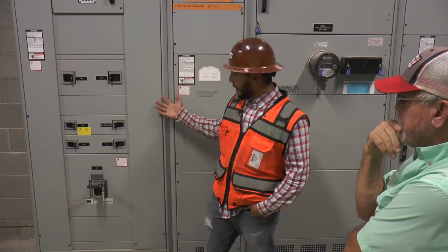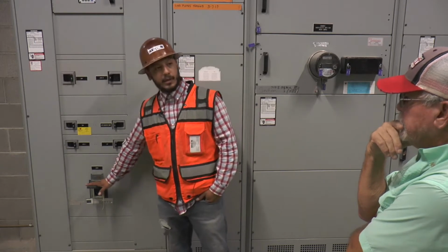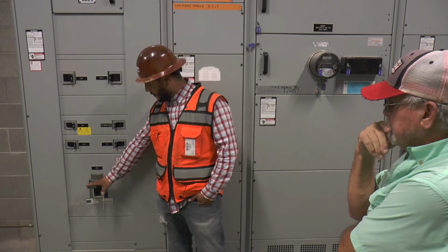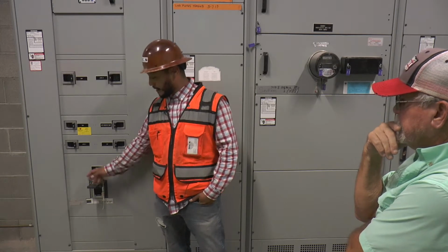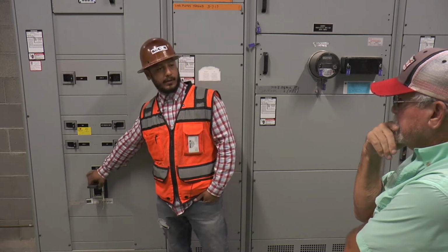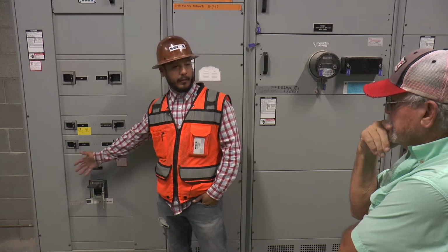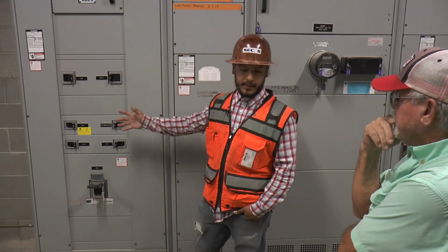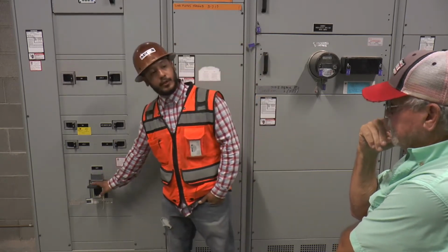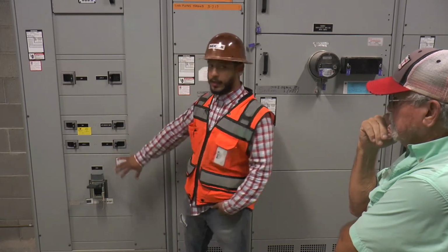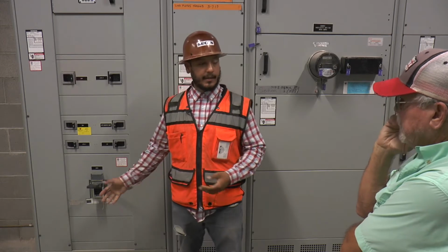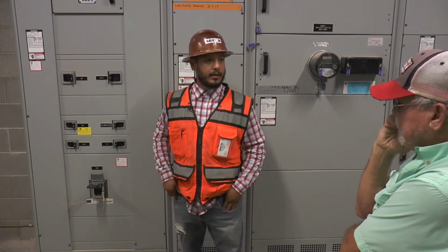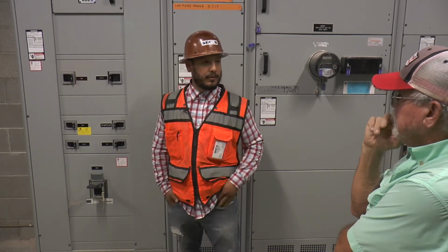So this is the main for the whole service. It shouldn't be, we could leave this on, but it shouldn't be really exposed like this. But if you need to test the system, this is a main breaker that you could just test instead of switching all of them on to make sure all the EM circuits go on all at once. 10-second, no more than a 10-second delay. I counted it, it was 6 actually when it lit back up.